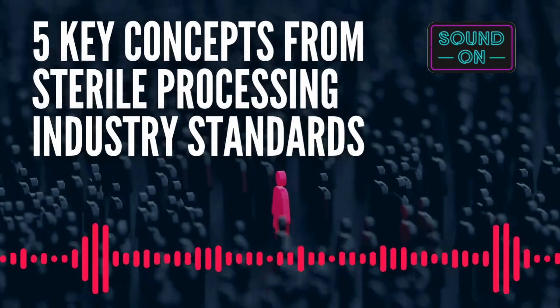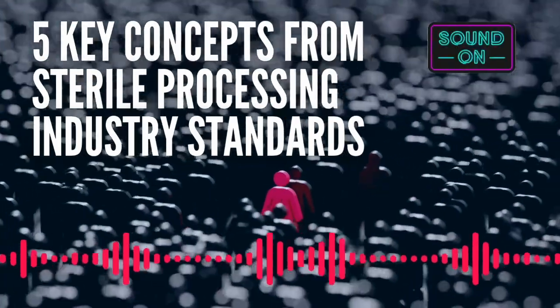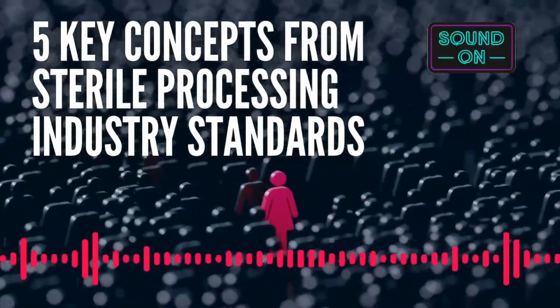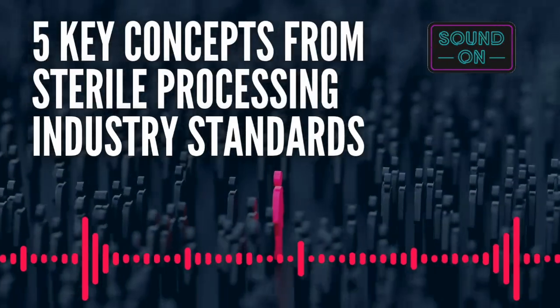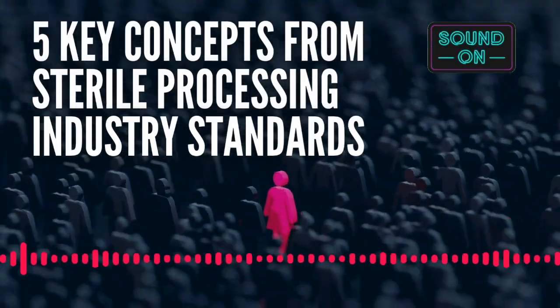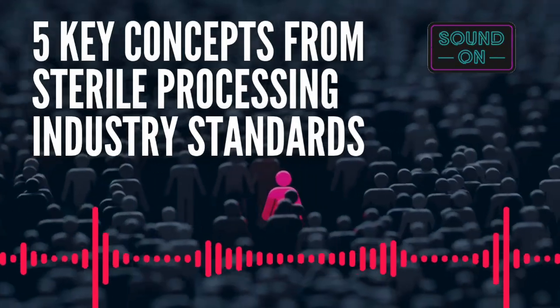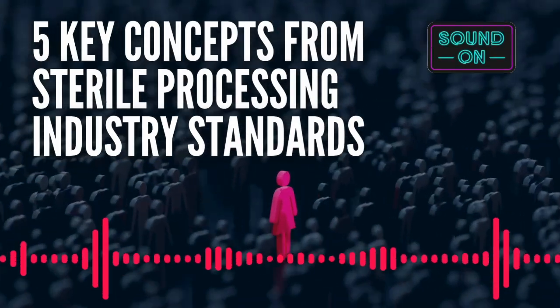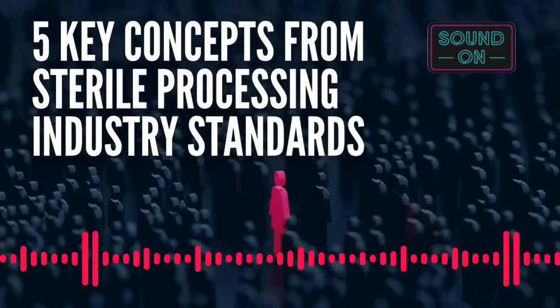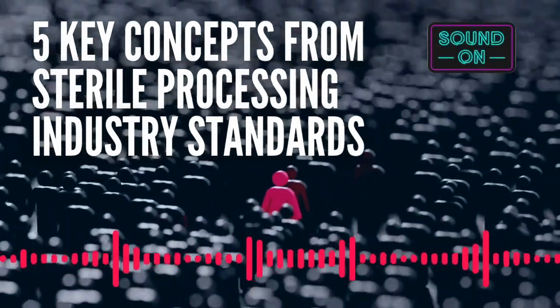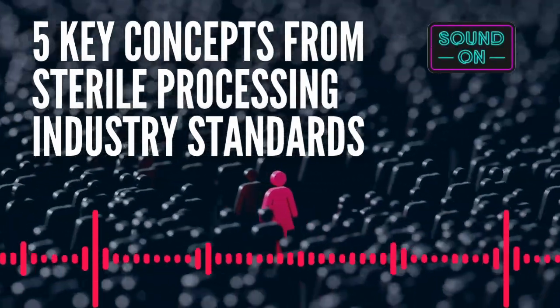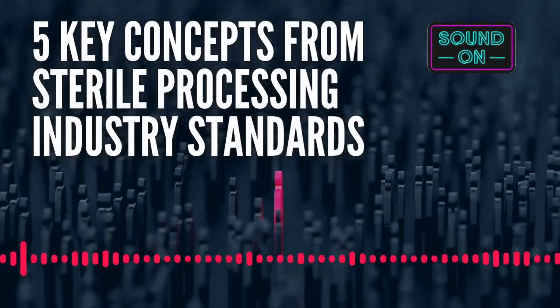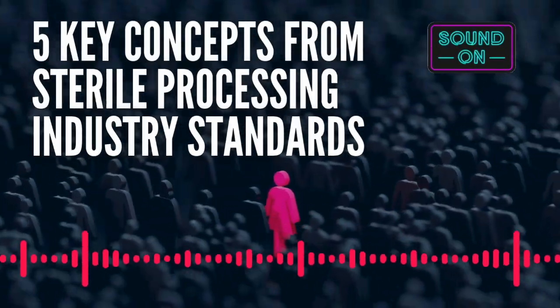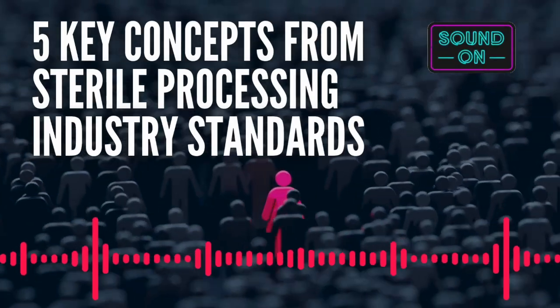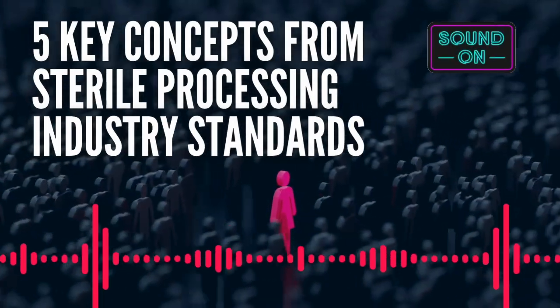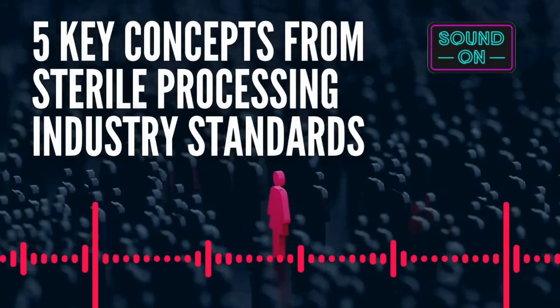Well, one big one is regular testing of all our mechanical cleaning equipment. So like those ultrasonic cleaners and washer disinfectors? Yep, got to make sure those machines are doing their job, getting rid of all that debris and bioburden. So it's like giving them a regular checkup. Exactly. We want to make sure they're running smoothly and efficiently. And how do we do that? Well, there are specific verification tests that we can use. Okay, so we're not just eyeballing it. No, we need objective data to prove that our equipment is performing as it should. Got it. So that's one part of the monitoring puzzle.